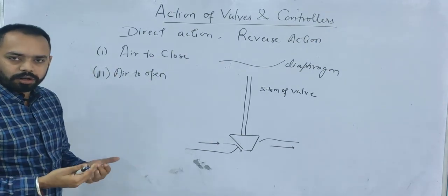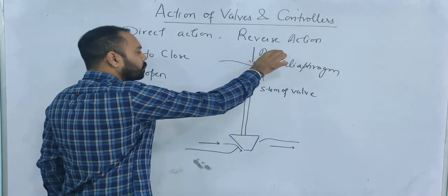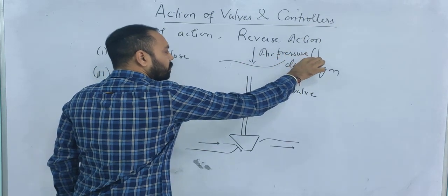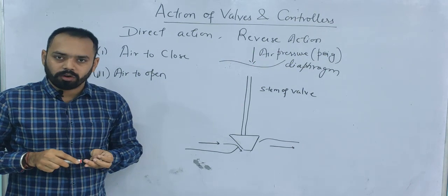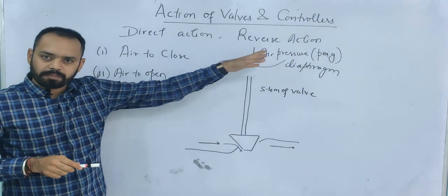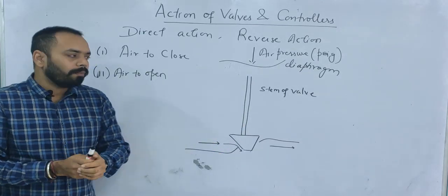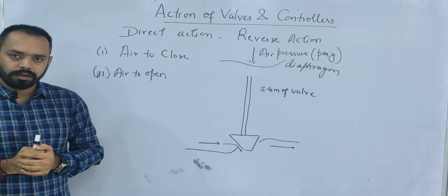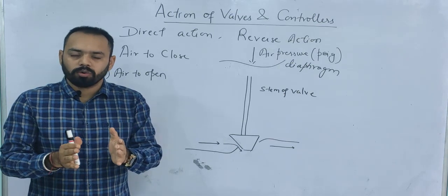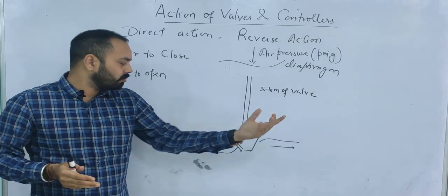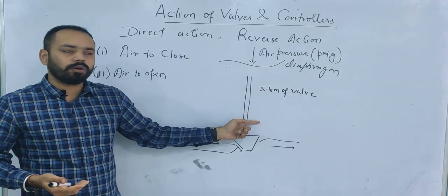If you talk about the classification of valves based on their working — based on the relation between the input air pressure, which is mentioned in psig (g stands for gauge pressure) — these kinds of valves which work on air pressure are called pneumatic valves. In these valves the input is the air pressure, and then you see whether the flow rate increases or decreases. Based on that we have two classic types: air-to-close valve and air-to-open valve.